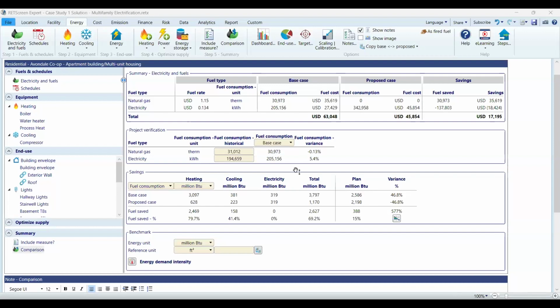The next is replacing exterior lights with 54 watt LED lamps with daylight sensor. So I go to the exterior lights. I change the metal halide to LED. Initially, they had metal halides at 175 watts. I'm now replacing it with a 54 watt LED, assuming there are no miscellaneous losses. But they also have daylight sensors, so the 24 hours goes down to 12 hours, assuming a 50% reduction in run hours. And that gives, just within the exterior lights, a saving of about 85% electricity.